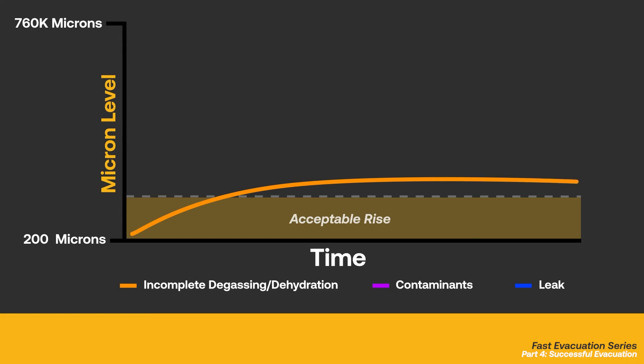Now, if the rise trend is similar but equalizes considerably higher, this indicates that there may be contaminants or moisture in the system, which may require a nitrogen sweep and a second evacuation.